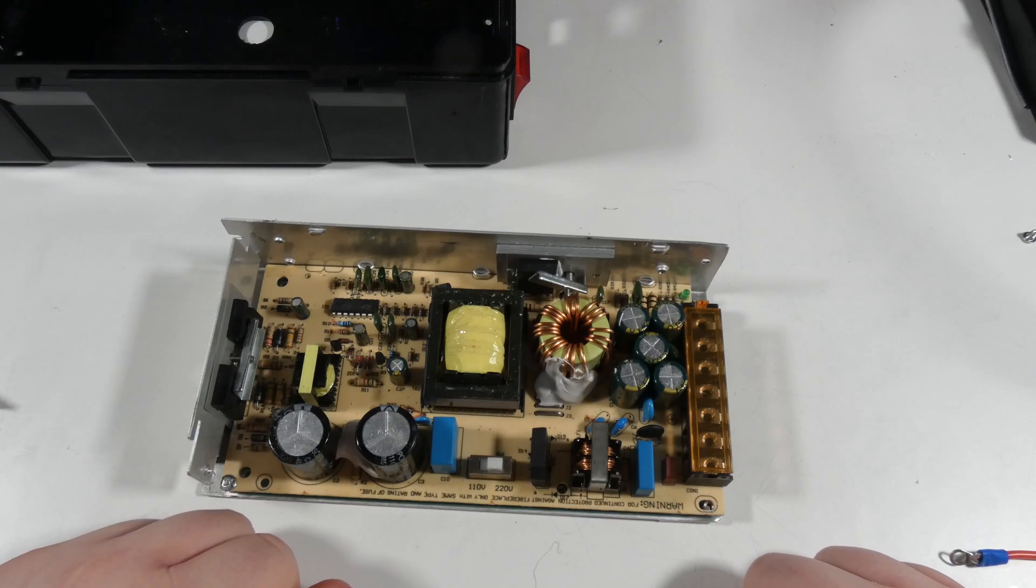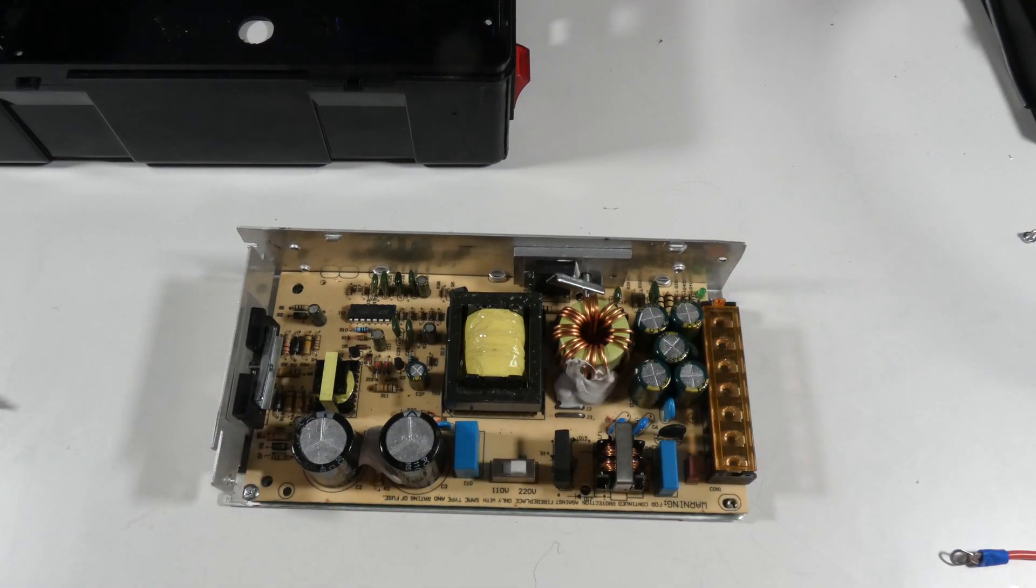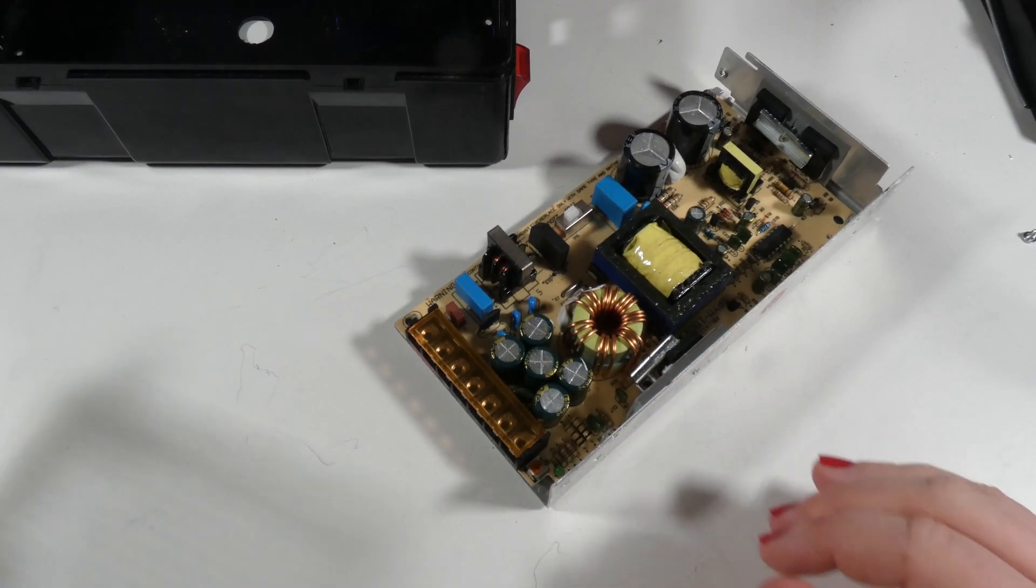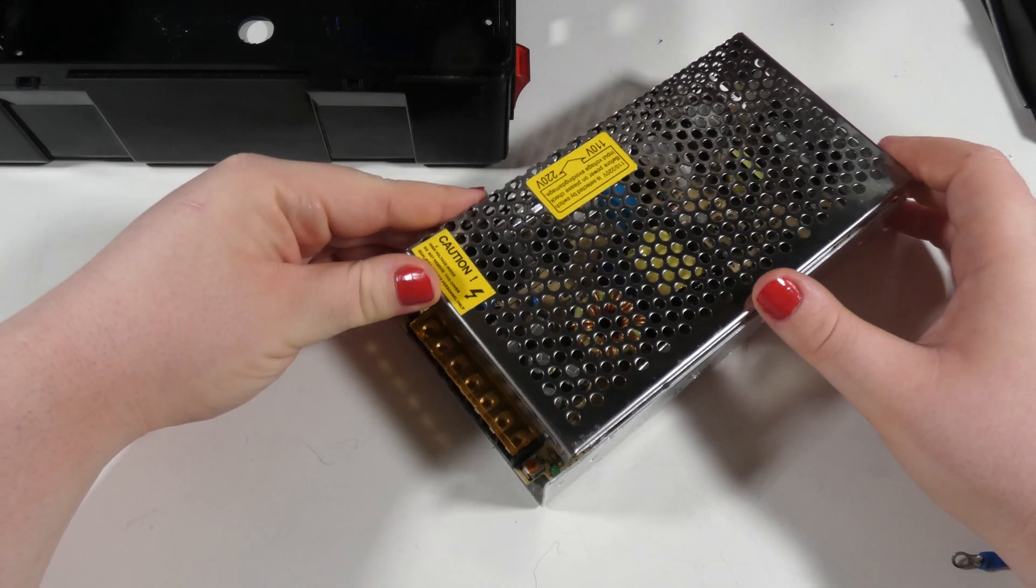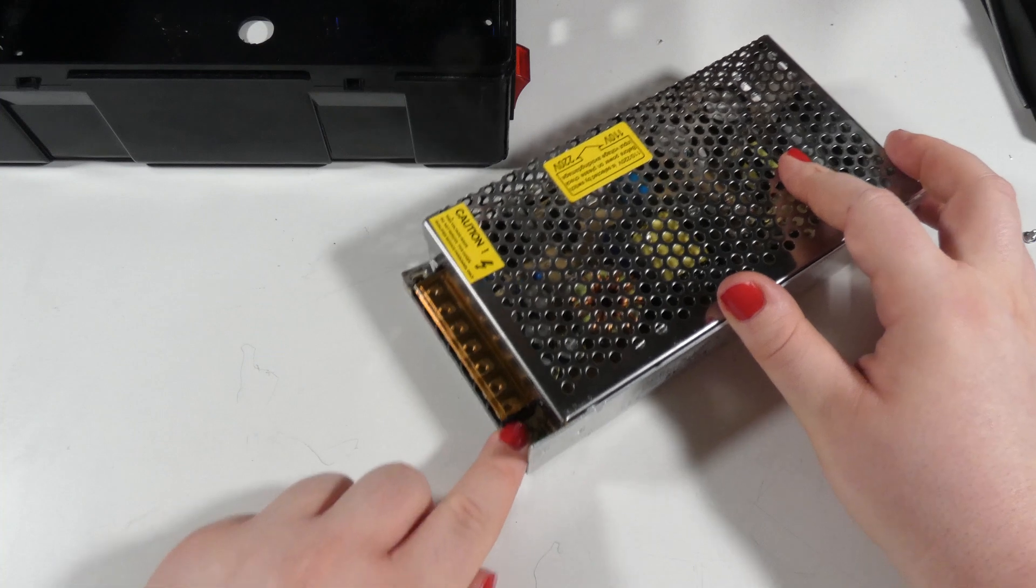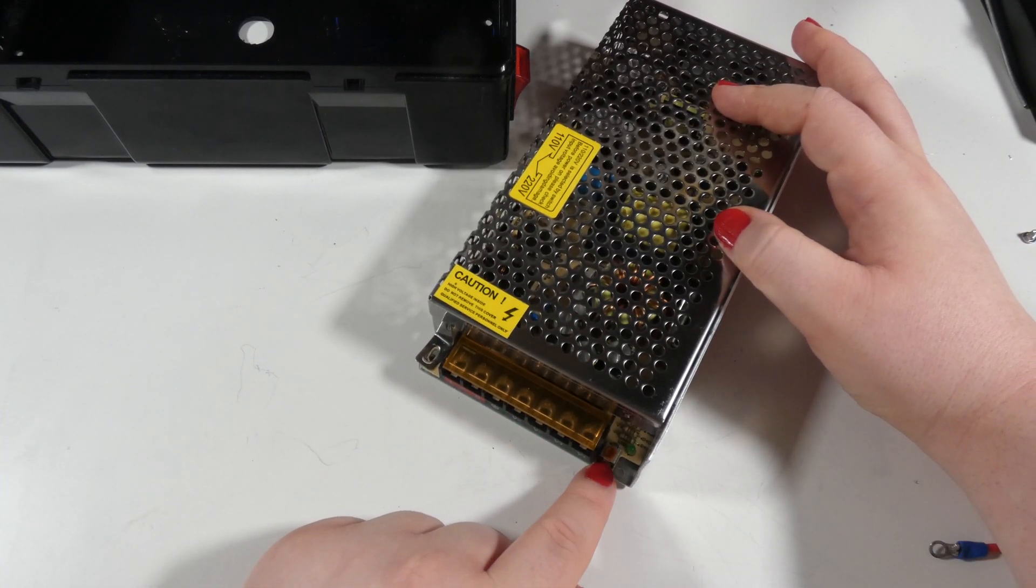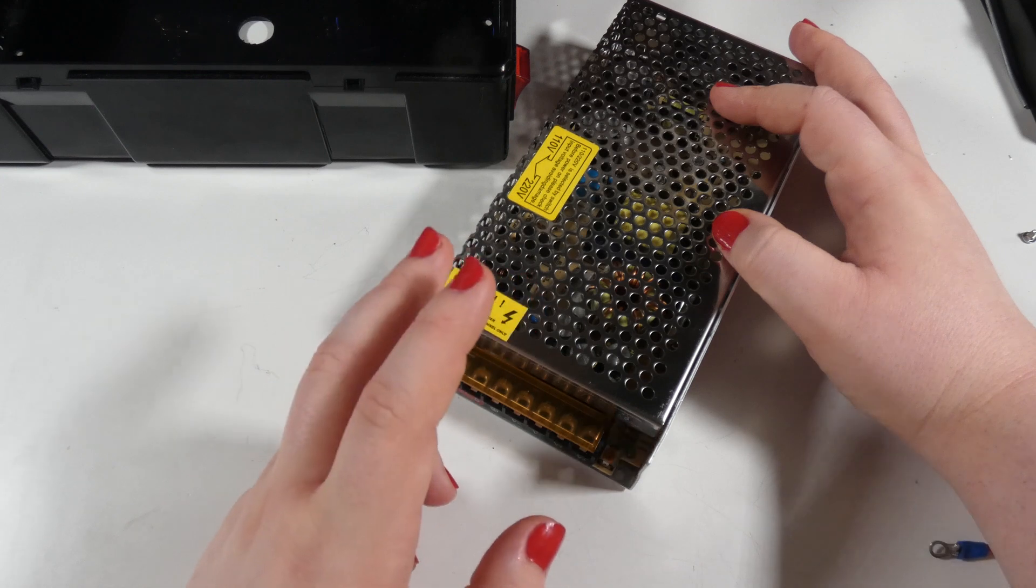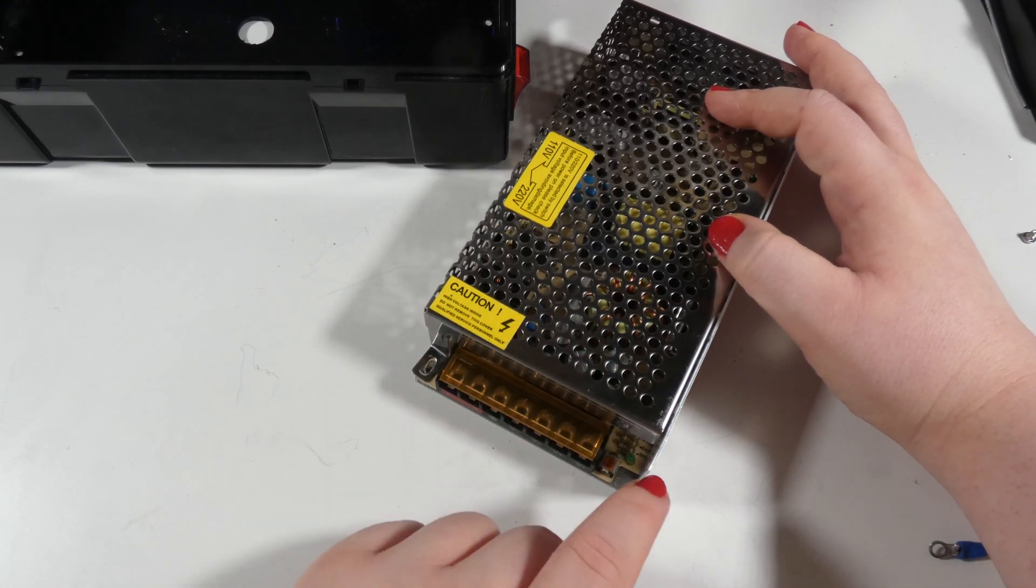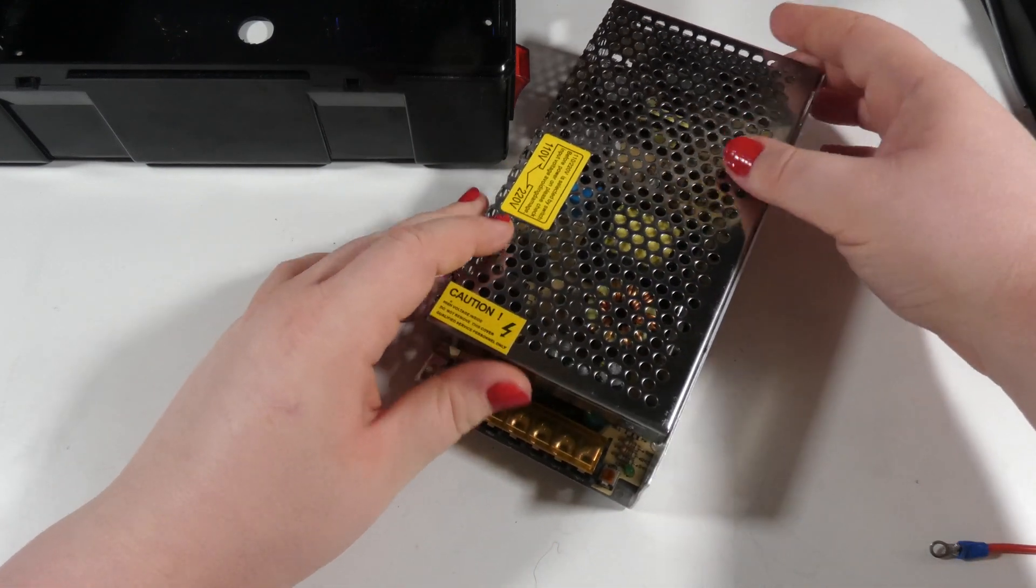This is not in any way changing the electricals. I'm not touching the electricals. The only thing I will do is use this potentiometer over here, but you are allowed by the manufacturer to touch this. The cover sits in here, and you can get access to this potentiometer even if the cover is on. This is to be used to readjust the secondary side, the five volt voltage, depending on load. If you were to pull 30 amps, you would have a significant voltage drop, and we can use this potentiometer to get the voltage back up.